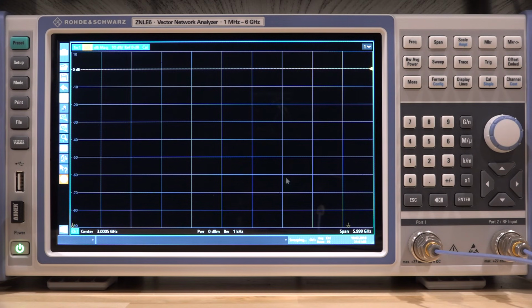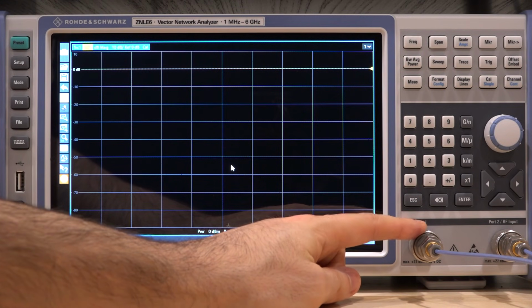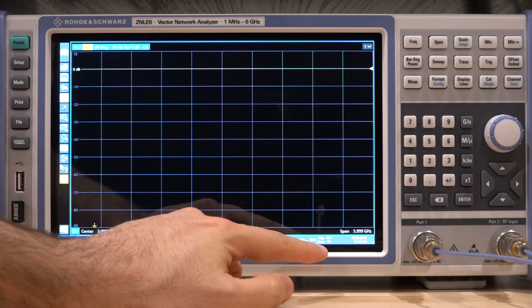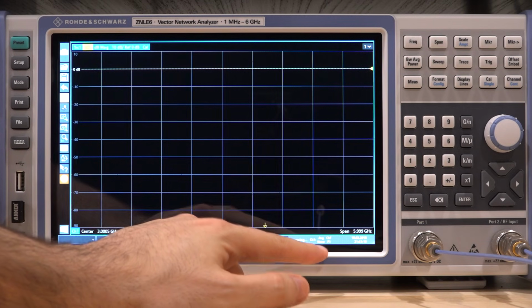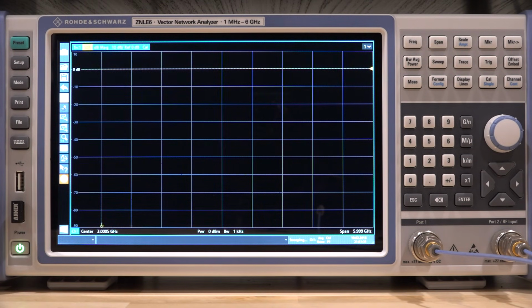So the instrument has one other minor sweeping issue that's a little bit frustrating. First of all, I really like it when instruments have a light that shows which port has the incident power. This one doesn't have a light on the front of the unit itself, but it does show it here at the bottom. If you look very carefully, it tells you which port is the incident port where it's receiving power. So you can see right now it's jumping between port 1 and port 2. Now, even though I'm not asking for it to display anything that requires incident power from two different ports, it's still doing both of the ports at the same time.